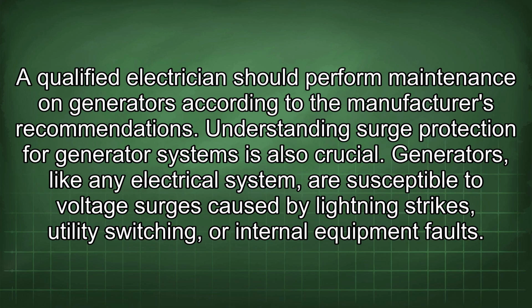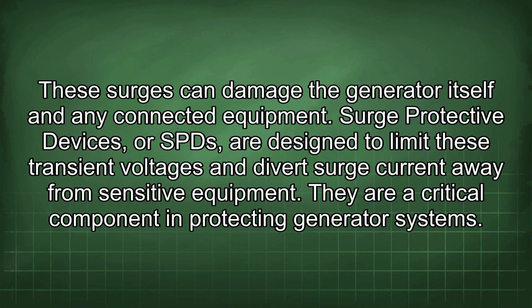Understanding surge protection for generator systems is also crucial. Generators, like any electrical system, are susceptible to voltage surges caused by lightning strikes, utility switching, or internal equipment faults. These surges can damage the generator itself and any connected equipment. Surge protective devices, or SPDs, are designed to limit these transient voltages and divert surge current away from sensitive equipment. They are a critical component in protecting generator systems.